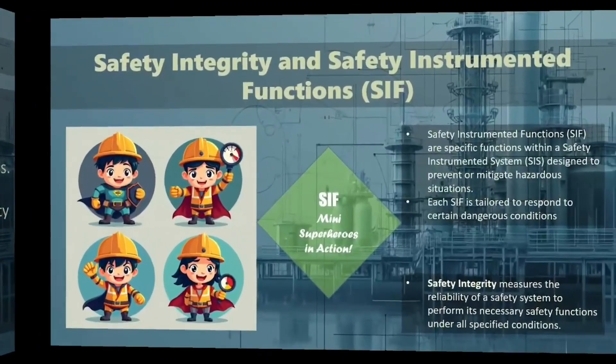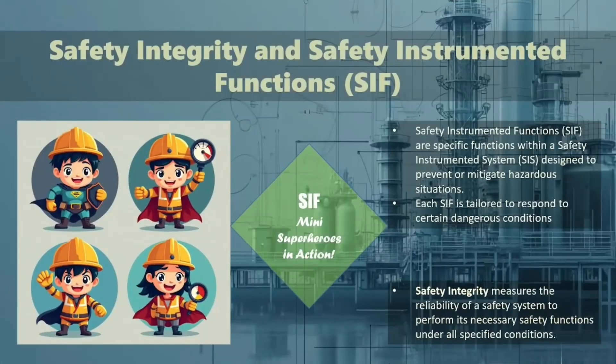Safety instrumented functions, or SIF, are specific functions within a safety instrumented system, or SIS, designed to prevent or mitigate hazardous situations. Each SIF is tailored to respond to certain dangerous conditions, such as shutting down a system if it detects unsafe operating parameters. Safety integrity measures the reliability of a safety system to perform its necessary safety functions under all specified conditions, ensuring that safety functions perform correctly when needed. Each SIF is like a mini superhero within the SIS, tasked with specific safety duties like preventing a machine from overheating.